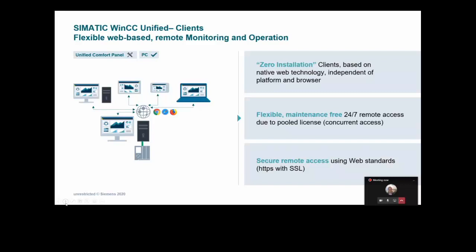The full HTML5 client is fully supported on the PC-based platform, but not currently on the Unified Comfort Panel platform. Going ahead, we will be releasing an update for the Unified Comfort Panels to support a client or a couple of clients directly on the panel. At the moment it's only a single local client for the panel. On the PC-based platform, we support up to 150 clients onto a single server. If you need more clients, just add more servers.